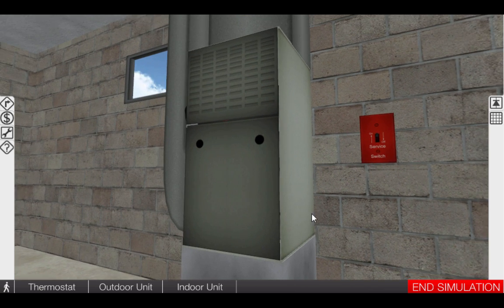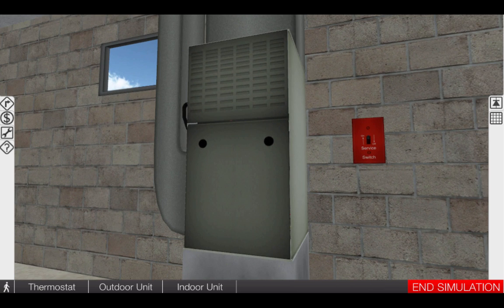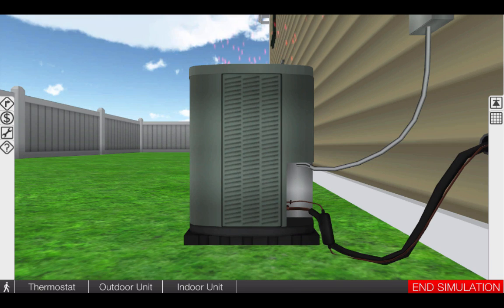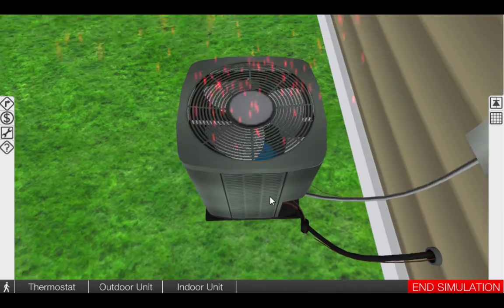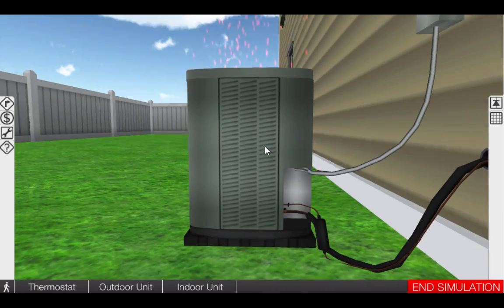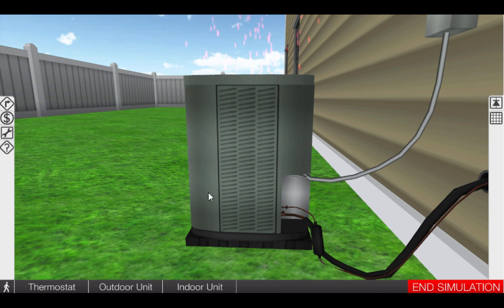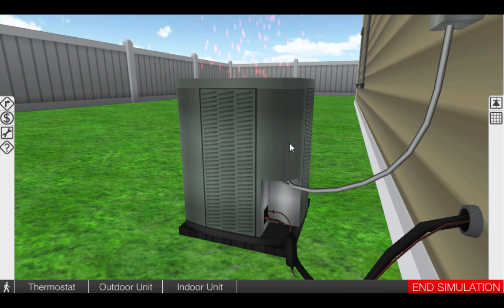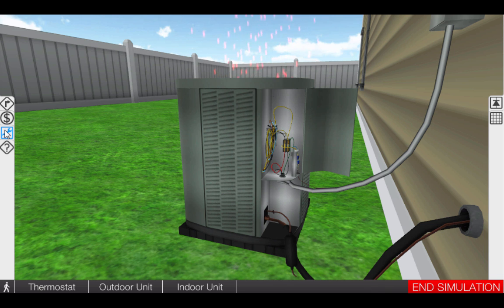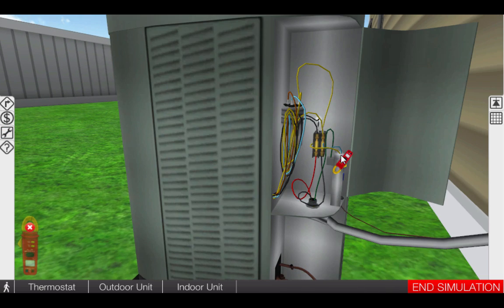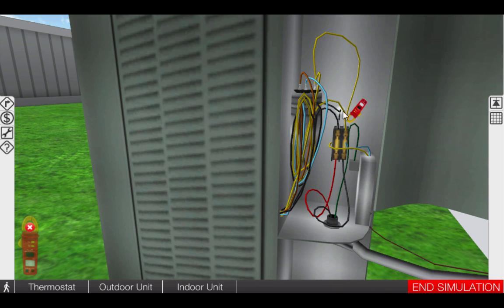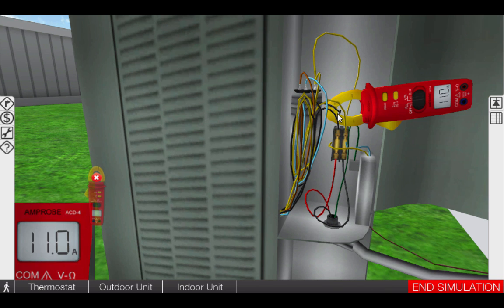Next, we need to go to the outdoor unit to verify that the compressor and condenser fan are running. Click on the outdoor unit icon. Once at the outdoor unit, we can see that the condenser fan is running and we can also hear the compressor operating. Open the control box and click on the clamp-on ammeter to verify that the compressor is in fact operating. We can see we do have a current draw of 11 amps.